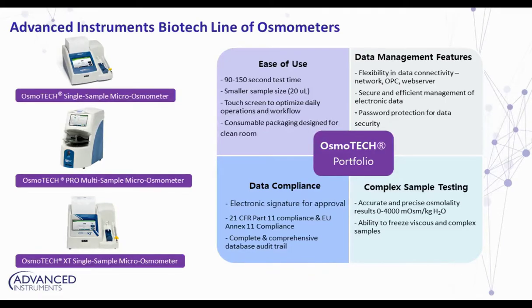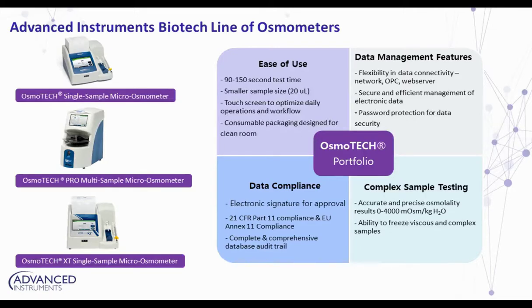With the Osmotech XT, we can now test even more sample types. Samples that may have previously been more of an issue with our technology now show the same performance and robustness as we'd expect from any AI instrument. With the XT, you can run up to 4,000 milliosmoles per kilogram, and you have the ability to freeze more viscous and complex samples. Tara, since you are a user of Advanced Instruments, could you speak for a moment to the robustness and reliability of the instrument?